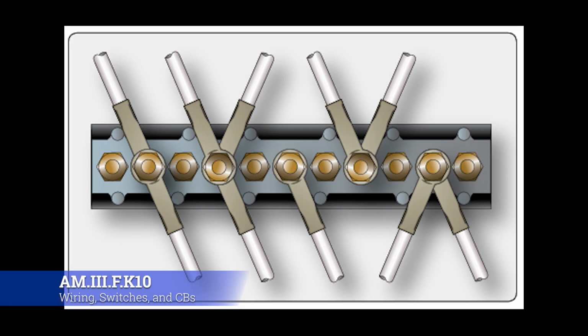Now, once the torque hits its inflection point, it's going to want to grab that lug and turn it. It should be turning - it'll turn away because you're tightening it down, away from that post. But you're going to have to hold your finger on that post as you're tightening down the lug. It should stay right there on that non-conductive post, so it doesn't spin off and go somewhere else. If you do every single one of them that way, you will create enough space so that there's a very low chance something gets in between the two of them.